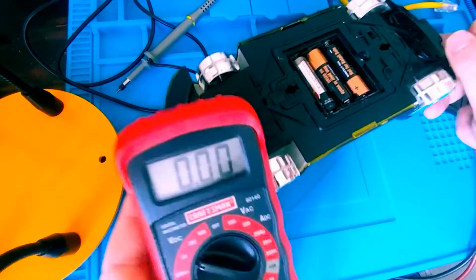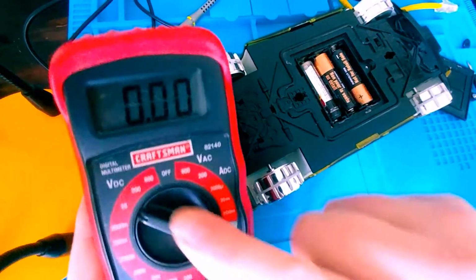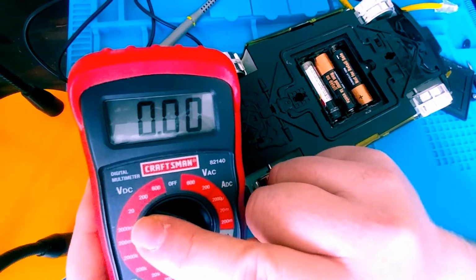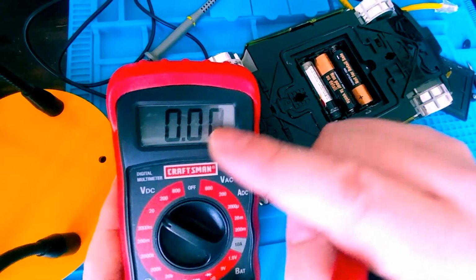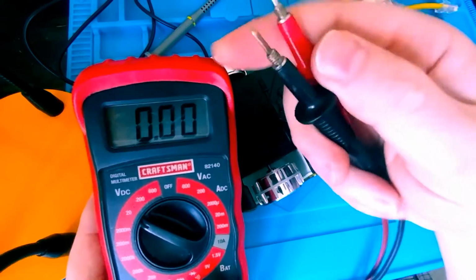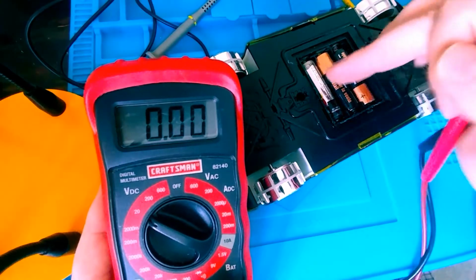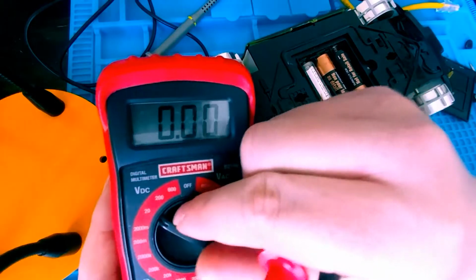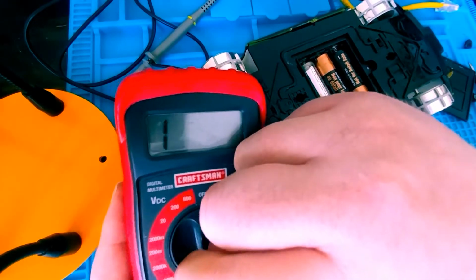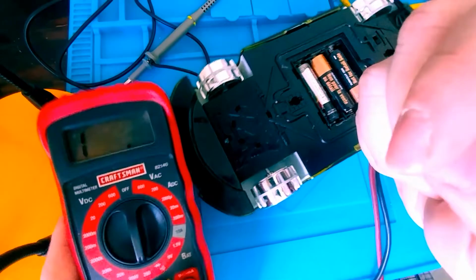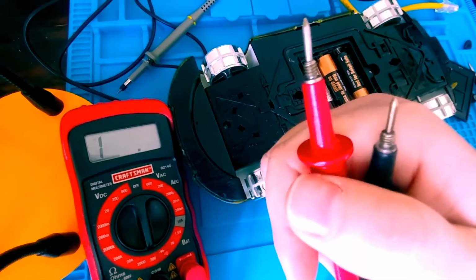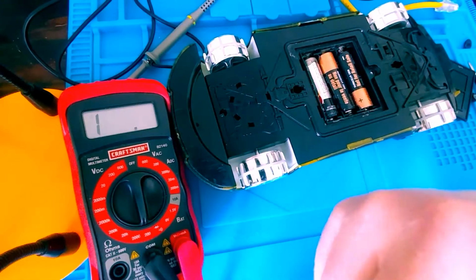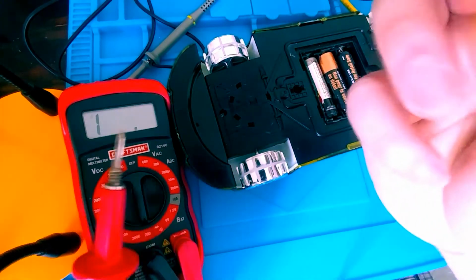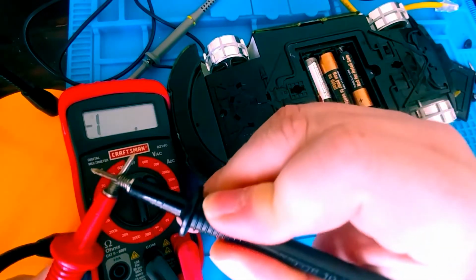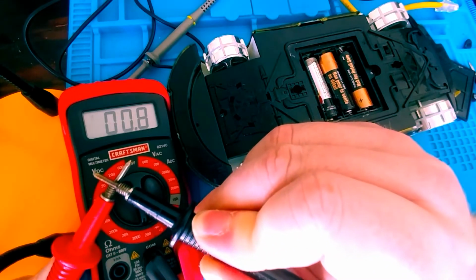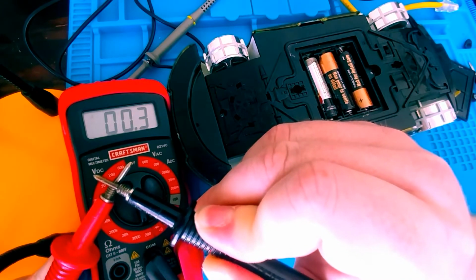One way is with a multimeter. If I set it to volts DC, on a low range of that scale, 20 volts DC, I can make a measurement with my negative lead and my positive lead across these batteries. Now, something I often do on the job out of practice is ensure my leads are good, by setting them to the low scale for an ohms or continuity measurement, and touching my leads together. There should be little to no resistance across the leads.